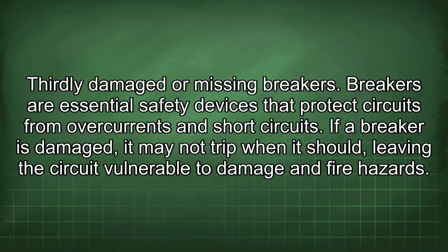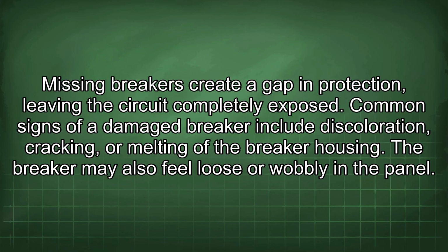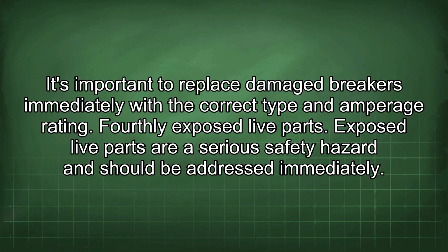Thirdly, damaged or missing breakers. Breakers are essential safety devices that protect circuits from overcurrents and short circuits. If a breaker is damaged, it may not trip when it should, leaving the circuit vulnerable to damage and fire hazards. Missing breakers create a gap in protection, leaving the circuit completely exposed. Common signs of a damaged breaker include discoloration, cracking, or melting of the breaker housing. The breaker may also feel loose or wobbly in the panel. It's important to replace damaged breakers immediately with the correct type and amperage rating.